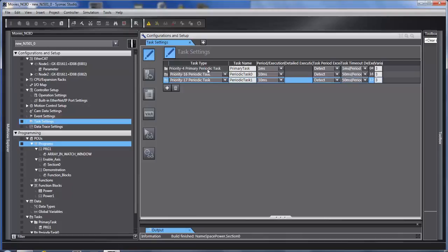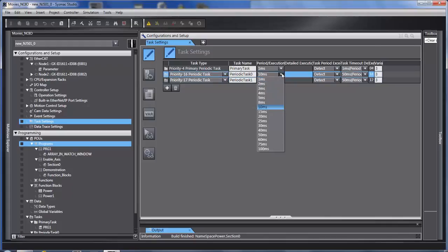The secondary place you can put the code is in priority 16 periodic task. It runs slower than the primary task. Basic choices of 1 to 100 milliseconds, but never faster than the primary task.